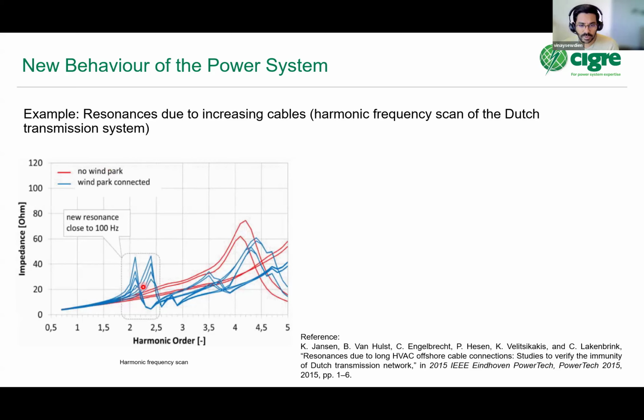So what you can see here, focus on the red lines. That is the normal harmonic impedance of a part of the power system. Now, there were plans in the Netherlands to connect a wind farm. In order to connect that wind farm, there was a need to upgrade the power system, and the additional investments would require an underground high voltage AC cable. High voltage AC cables are capacitive. So the system operator did a study, and they realized that in order to connect the wind farm, they needed to have that cable connected, and you can see that the resonance frequency shifts from approximately the 4th harmonic to the 2nd harmonic. So it brings it closer to its nominal value.